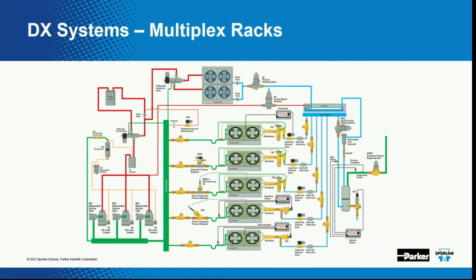That liquid refrigerant is going through a liquid header and then feeding all of the store cases. So it goes through the line to the expansion device, and that will expand the liquid from liquid to saturated. So when it goes into the coil, it's a liquid and vapor mix. When it comes out of the coil, it is completely vaporized, it's superheated, and that's what goes back to the compressors. The compressors compress vapor, they don't compress liquid. Hard to compress that stuff.